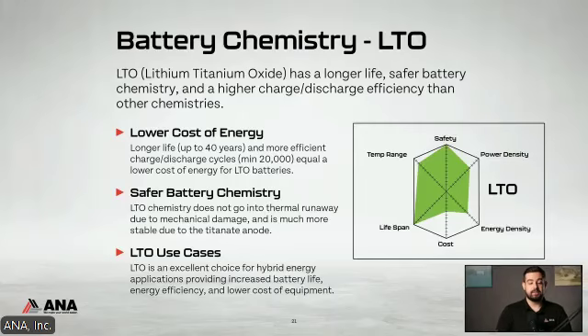So now we're at LTO. This is what ANA uses personally, lithium titanium oxide. They do have a very high cycle life, 10,000 to 20,000, could even go farther, but it just depends on the environment, right? But very high temperature range, -30 to 65 C, and high continuous C rates. So 3C and above, it can handle pretty continuously.